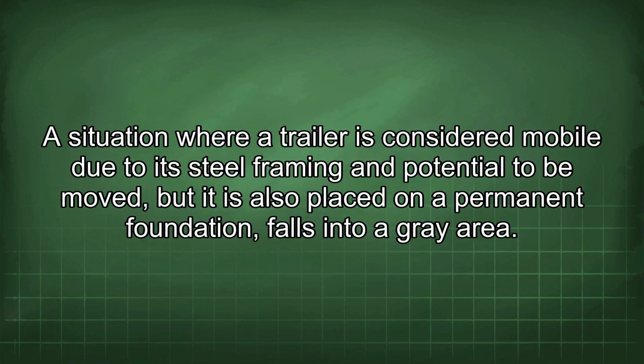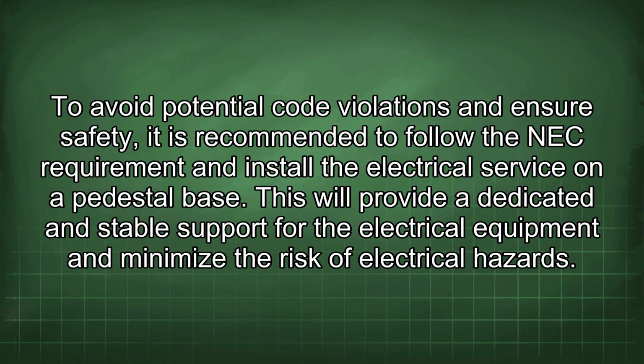A situation where a trailer is considered mobile due to its steel framing and potential to be moved, but is also placed on a permanent foundation, falls into a grey area. To avoid potential code violations and ensure safety, it is recommended to follow the NEC requirement and install the electrical service on a pedestal base. This will provide a dedicated and stable support for the electrical equipment and minimize the risk of electrical hazards.